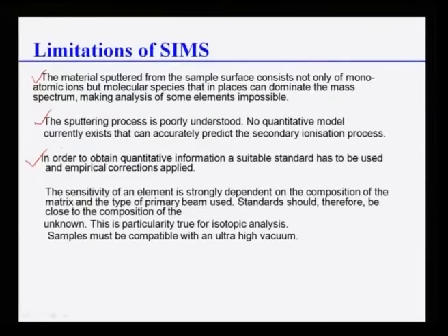So it depends on the matrix. We have shown that even the intensity is a function of the matrix. It is not linear with only the element present. And it also depends on the type of primary beam used. So standards should be close to the composition of the unknown. This is particularly true for isotopic analysis.